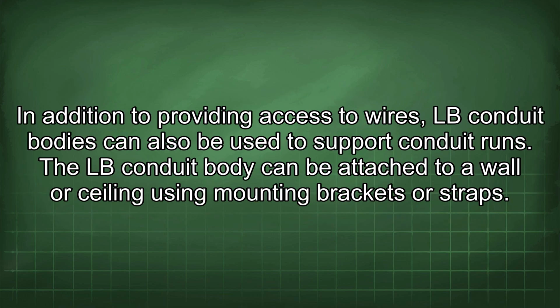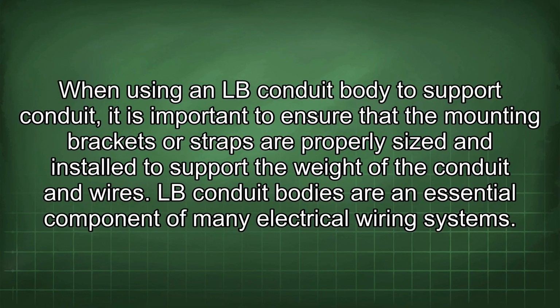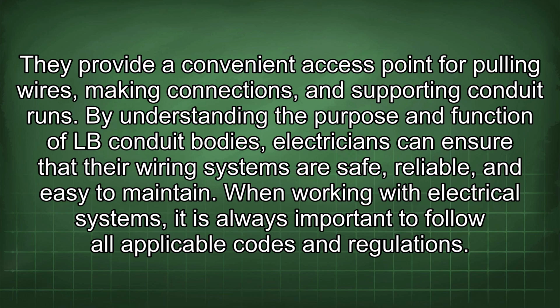In addition to providing access to wires, LB conduit bodies can also be used to support conduit runs. The LB conduit body can be attached to a wall or ceiling using mounting brackets or straps. When using an LB conduit body to support conduit, it is important to ensure that the mounting brackets or straps are properly sized and installed to support the weight of the conduit and wires. LB conduit bodies are an essential component of many electrical wiring systems. They provide a convenient access point for pulling wires, making connections, and supporting conduit runs.